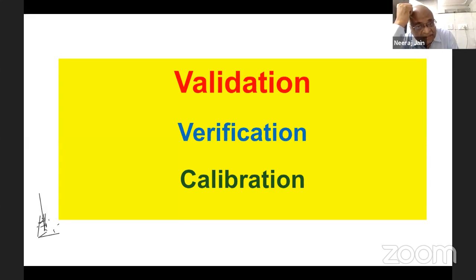How to differentiate? In validation, there is some claim. And in verification, there is confirmation of the claim. Suppose some company people are saying that in this machine precision for hemoglobin is 2%, the lower limit of detection is, say, 3 gram per dl, and linearity is up to 20 gram per dl. If they are saying so, that means they must have done some studies. Whatever they have done to make the claim is called validation, and those are called validation studies. Suppose they say this machine has a throughput of 100 tests per hour; whatever they have done is called validation. And if you are checking in your laboratory to confirm their claim, then it is called verification.